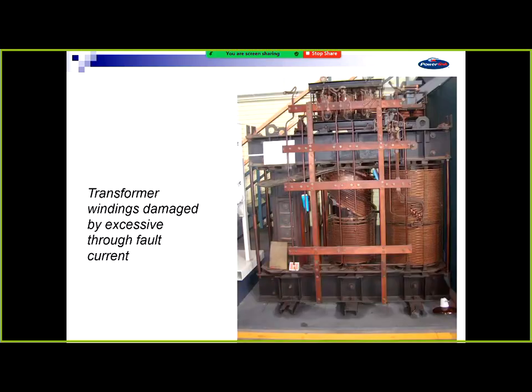This is an old one that sits in the workshop at Powerlink, that we took a photo of and put in here. That's a transformer fault. That's the damage to the windings internally. It's not used for anything but archive purposes, and will probably go into a museum one day. But it's interesting, you can see the forces there that have just shifted the windings internally. So they can be quite strong, the forces.